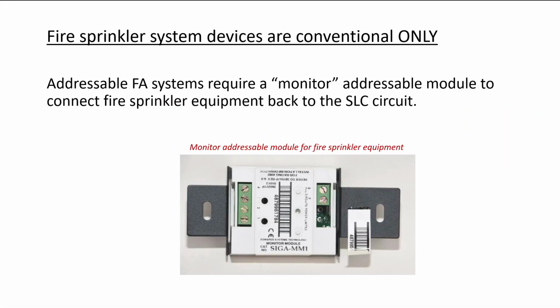Fire sprinkler system devices are conventional manufactured only. So that means addressable fire alarm systems require the monitor addressable module to connect that equipment back to the SLC equipment or circuit. Now remember, a monitor addressable module is for use with detecting type devices and to connect those conventional devices back to an addressable system. Now there's a couple of different variations on this. I'm simply going to show you two very common types out in the field.